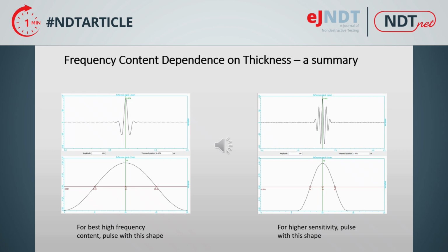Slide 6 illustrates that even relatively high attenuation through thicker sections can be addressed with the proper selection of an initial pulse. So if the higher resolution of a high frequency content is required, the clue is to start with a well-damped, high bandwidth probe and adjust the pulsar to optimize bandwidth rather than trying to maximize energy output. When using a negative square wave pulsar, improved results will be had by shortening the pulse length and, if available, adding a bit of electronic damping to the pulsar.